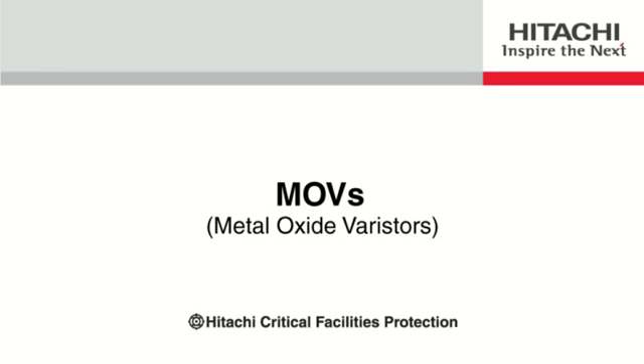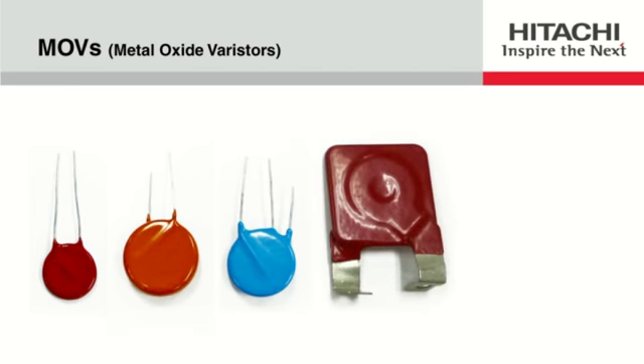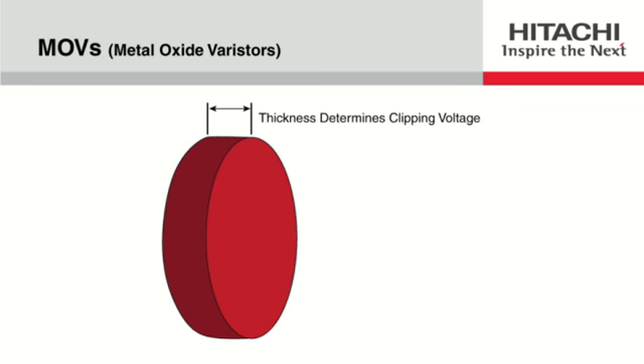Most SPDs utilize metal oxide varistors, commonly known as MOVs, as their principal surge protection element. MOVs are a variable resistor, meaning they change resistance depending on voltage. When voltage rises, MOVs become the path of least resistance to transfer surge energy out of the system.